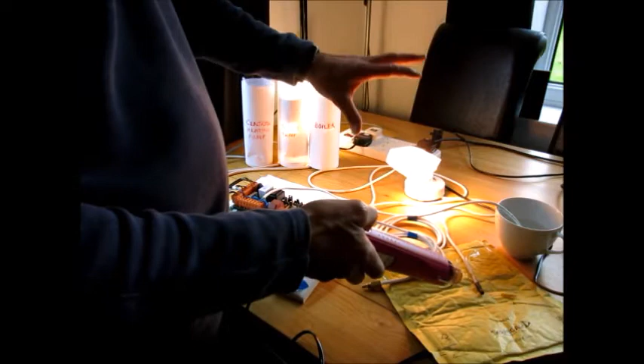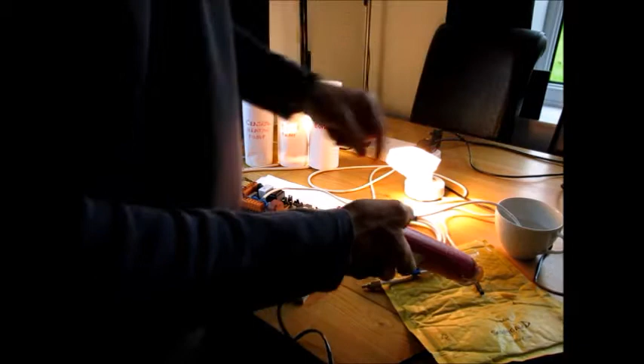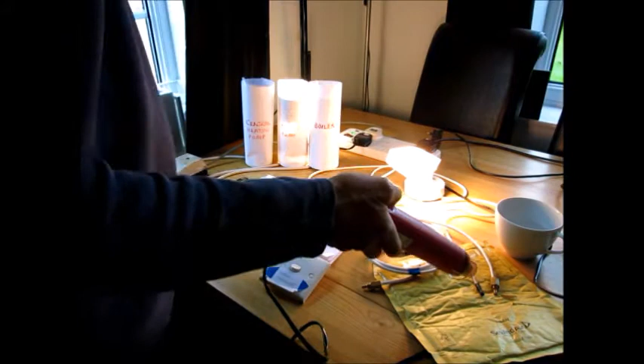Now this is what they call modulated. So it actually comes on faster and faster to pump more hot water through the plate heat exchanger to try and heat up the hot water. Obviously this cup's cold water, so it thinks I need to go at full speed. If I take this out now and just put it back on here and warm it up again, you'll see this will slowly ramp down. That's as though you shut the hot tap off and it's warming up the hot water again.